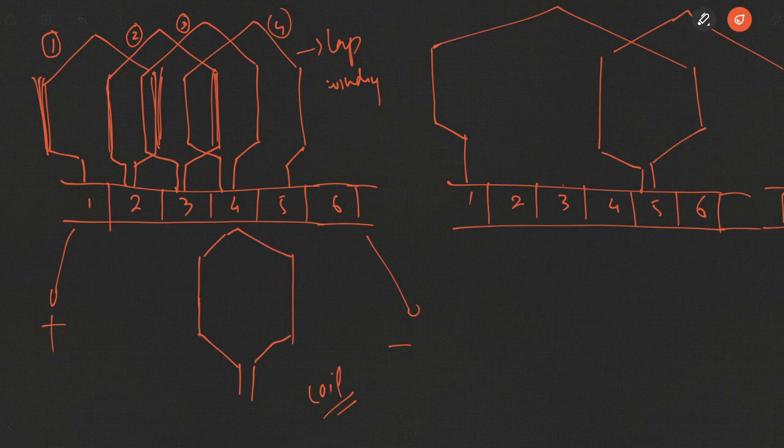windings can be arranged. Either it will be in this fashion, where each coil side is connected to the next alternate commutator segment, or in the second case, you have coil sides connected in such a fashion that they end up at some other commutator segment, whose information we do not have right now, but we'll be looking at where it will end up. We'll be looking at different equations associated with this. But what happens therefore is that in such a case, the machine no longer has lap windings. These windings are more like a wave, and that's why it's known as a wave winding.